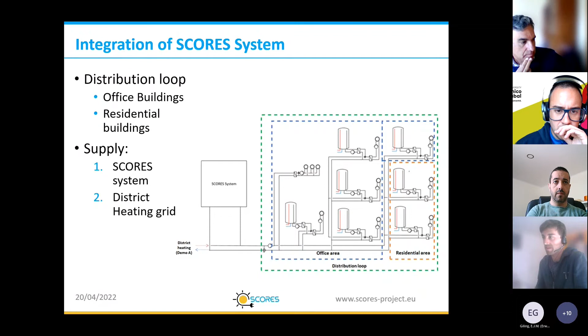So the technologies installed on site: we had a small collection of PV panels mounted on the roof of the container outside, and the heat pump system from Heliopac, which consists of 2 heat pumps at 12 kilowatts thermal supply each. They provide the SCORES buffer with heat at about 65 degrees Celsius, sufficient for both space heating and domestic hot water usage, fed to a 2,000 liter buffer. The district heating provides heat for both domestic hot water and space heating as a backup, and we also use the grid as a low temperature heat source for the evaporator side of the heat pumps.